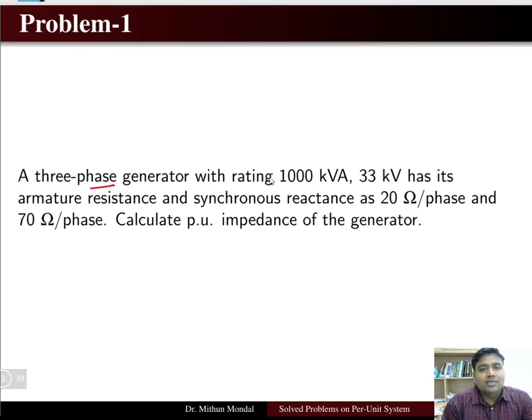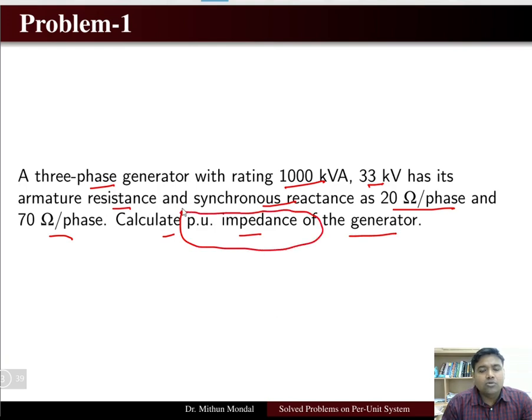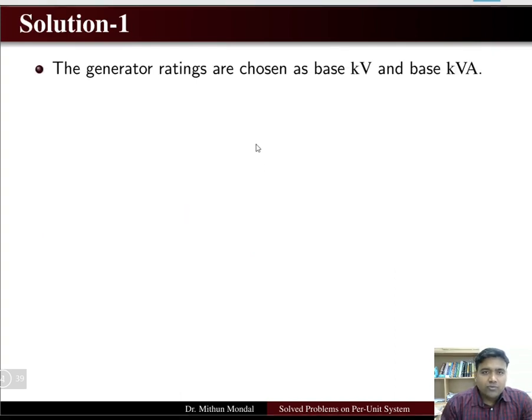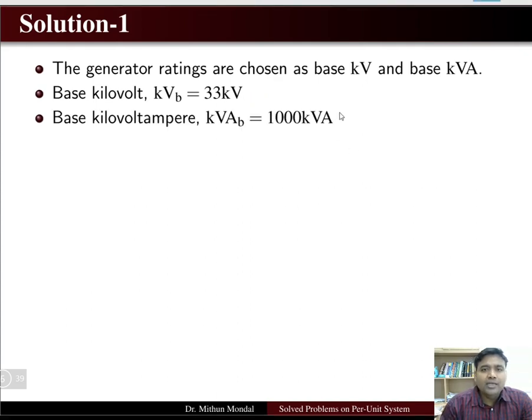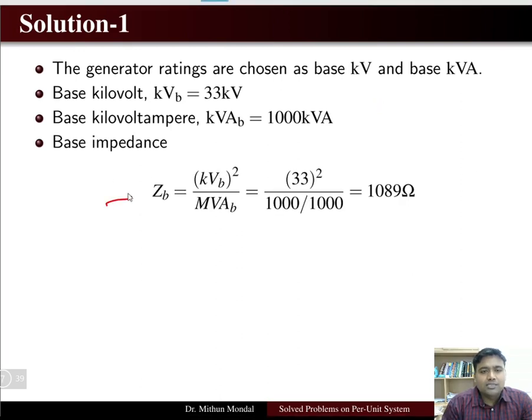Problem number one: we have a three-phase generator rated 1000 kVA, 33 kV. Its armature resistance and synchronous reactance are 20 ohm per phase and 70 ohm per phase respectively. Calculate the per unit impedance of the generator. We first choose the generator rating as the base, so base kV is 33 kV and base kVA is 1000.